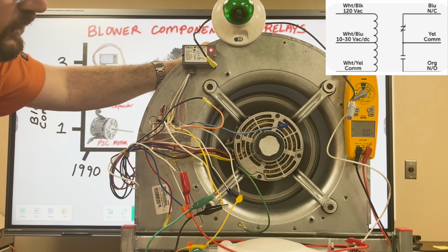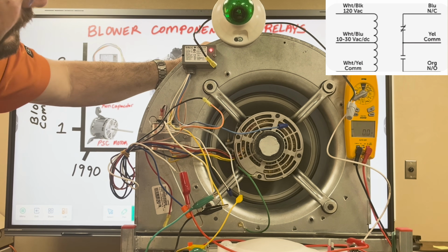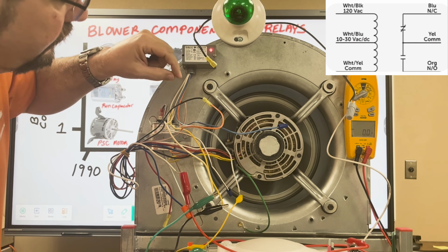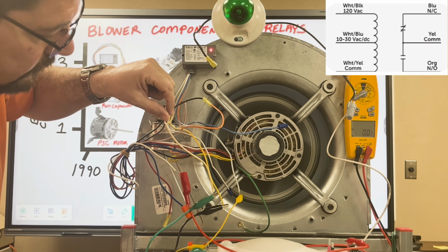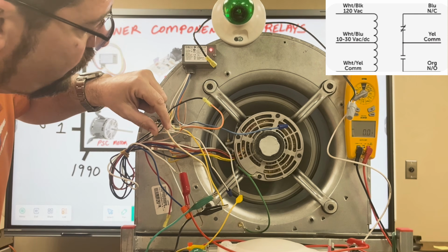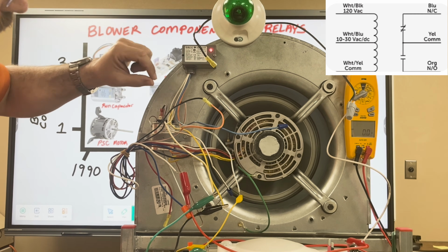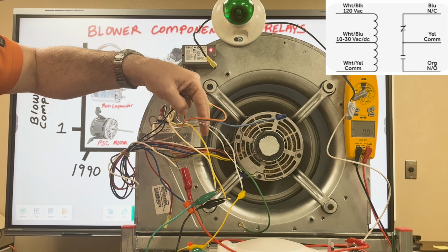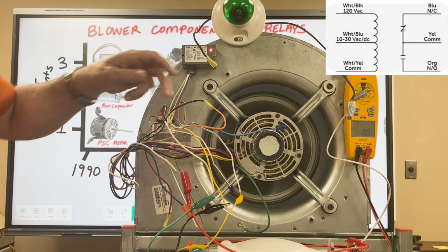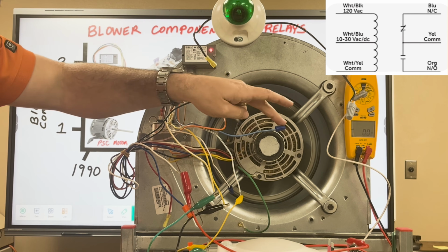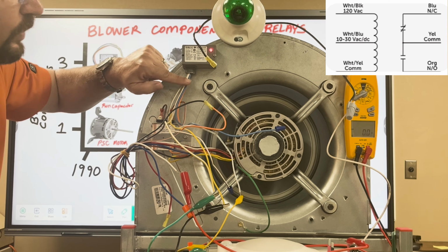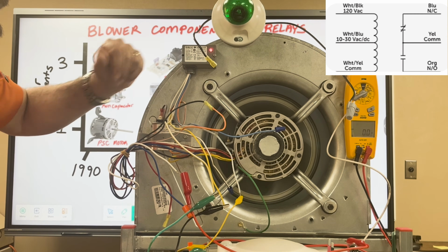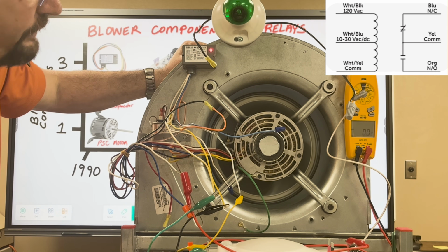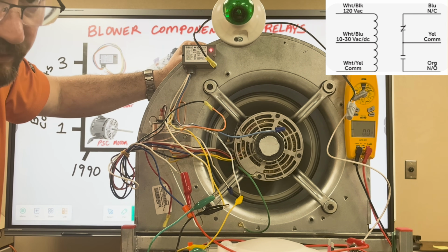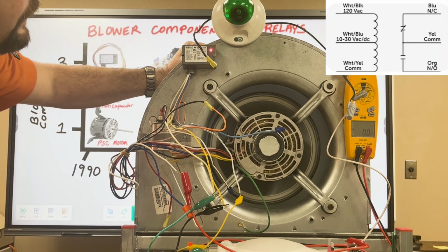And now any spare terminals that I'm not using, for example, let's see here. We have 1, 2, 3, 4. So all my spare ones that I'm not using, like this white/black, that's capped off, in my blue, which is normally closed contact, that's capped off. So out of the 6 wires coming out of this, I'm using 4. The other 2 are capped off. Make sure of that, because they'll be floating in your cabinet. You can't just use electrical tape. You need to cap them off.